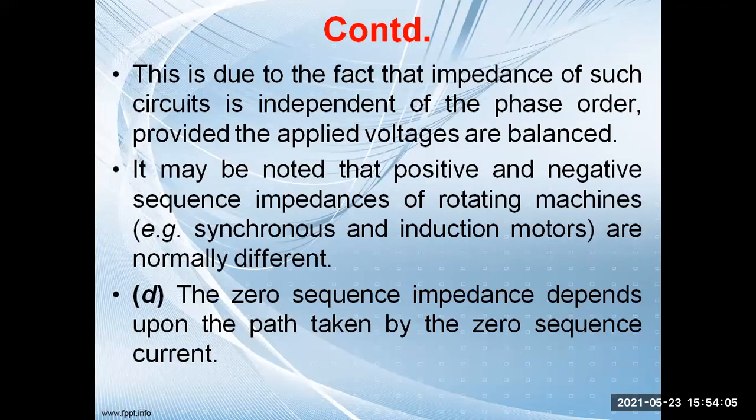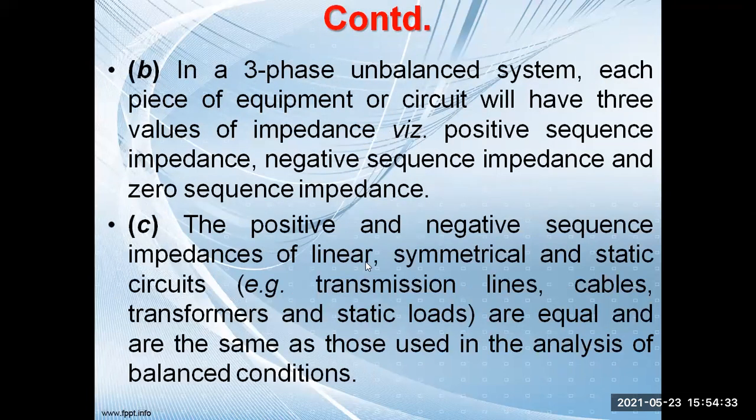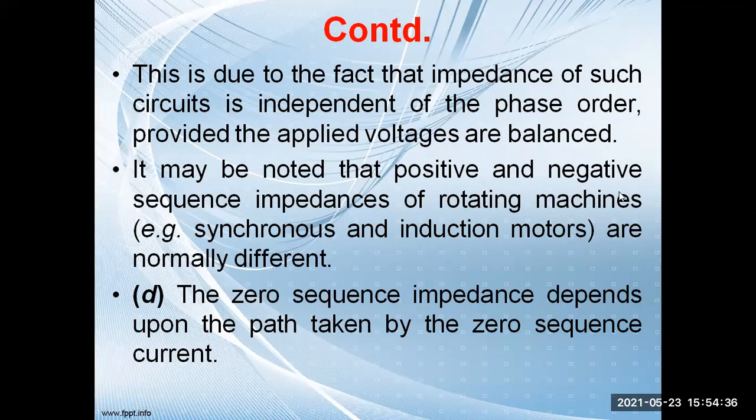Now, this is due to the fact that the impedance of such circuit is independent of the phase order, provided the applied voltages are balanced. So, if the applied voltages are balanced, then obviously it will not depend on the phase. Now, it may be noted that the positive and negative sequence impedances of rotating machines, like synchronous machines and induction motors, are different. For transmission lines, cables, static loads and transformers, the positive and negative sequence impedances are equal, but for synchronous machines and induction motors, they are not equal.